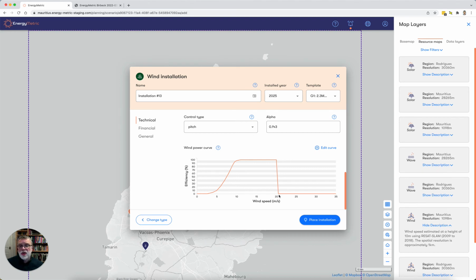So this is a typical wind power curve, and this is from the manufacturer specification. And our means of modelling wind is basically based around modelling this wind power curve. So what winds do we expect? How much power are we going to get? Again, there are much more complex and in-depth ways of modelling that, taking into account park effects, but at our pre-feasibility and planning stage, we're not too concerned with those features.